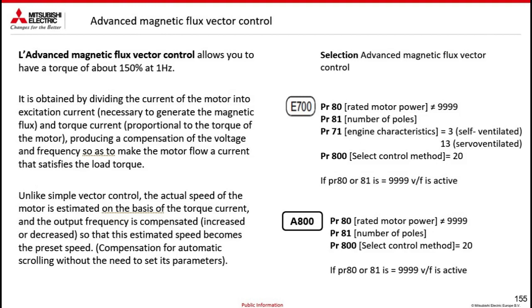The advanced instead, with which you can get 150% of torque at 1 Hz, is available for inverters that have the possibility to set the number of poles. The E700, E800, A800 and F800 inverters can do it. The tuning procedure is the same. I will only change the value. The parameter to perform the auto-tuning is 96. 96 can take various values.